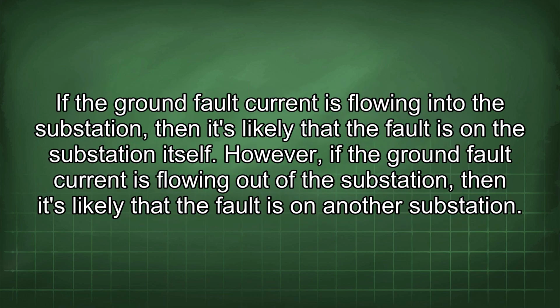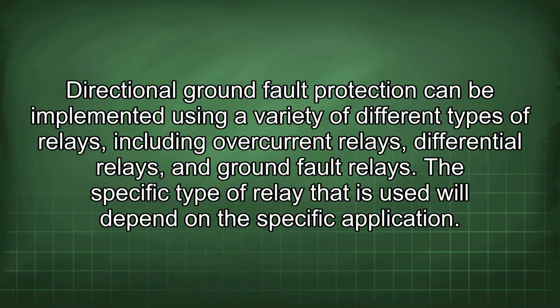If the ground fault current is flowing into the substation, then it's likely that the fault is in the substation itself. However, if the ground fault current is flowing out of the substation, then it's likely that the fault is on another substation. Directional ground fault protection can be implemented using a variety of different types of relays, including overcurrent relays, differential relays, and ground fault relays. The specific type of relay that is used will depend on the specific application.